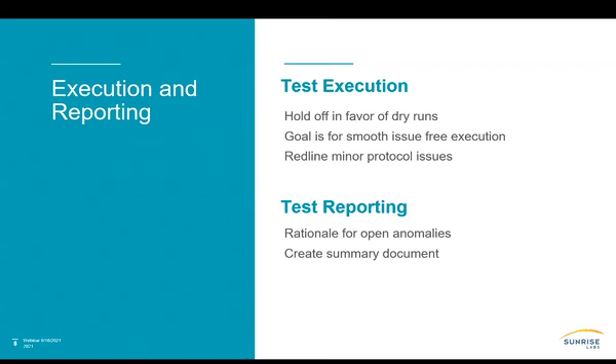If you find something during your formal execution, consider these issues and determine if you need to stop your execution altogether, or push through. In some cases, it's best to stop, log the issue, talk with your test manager, talk with your program manager, make note of it so that it's captured in the report, and start over once it's all been resolved. In some cases, it makes sense to continue, see if you find anything else that you need to address. Sometimes it's best to just get all the information up front. Hopefully your protocols are all clean, but if you run into a protocol deviation, redline it, log it, move on, and be ready to have it summarized in the report later on.